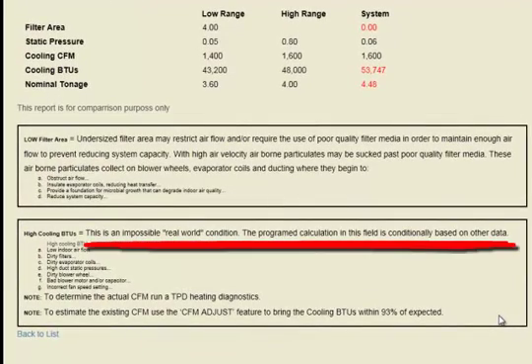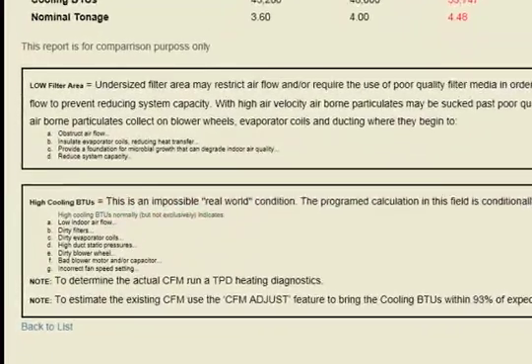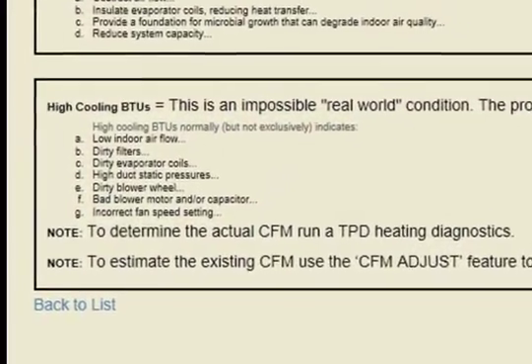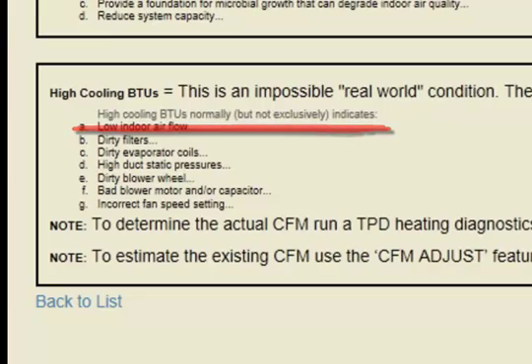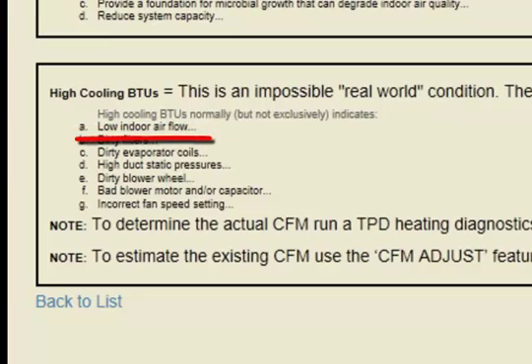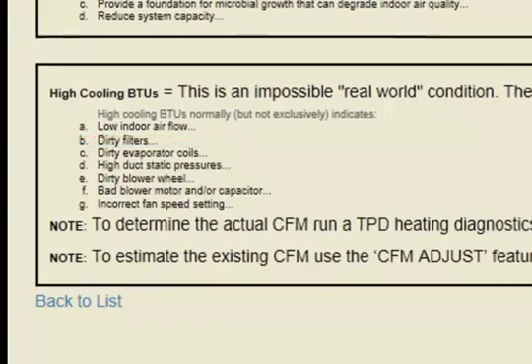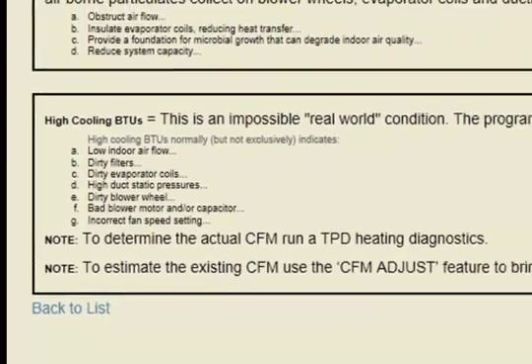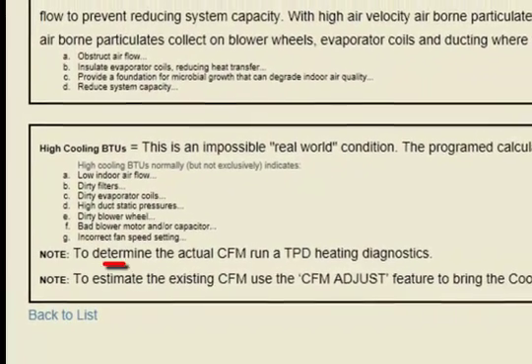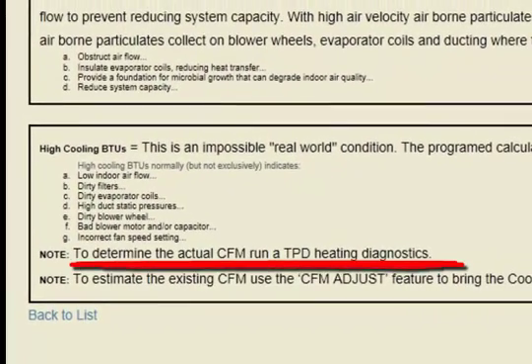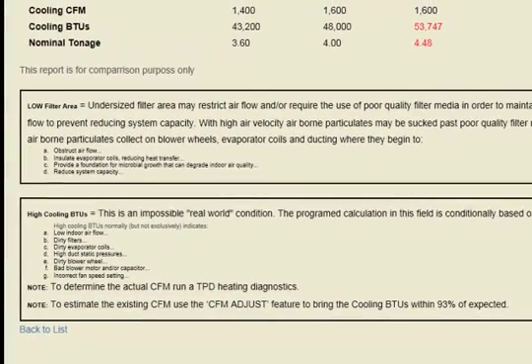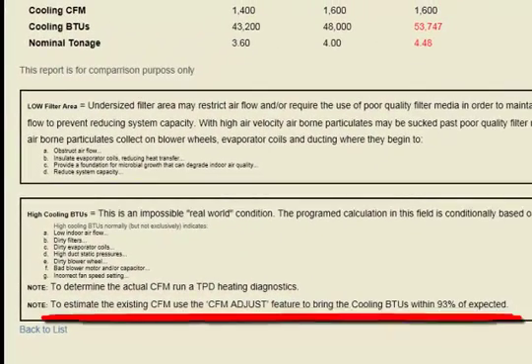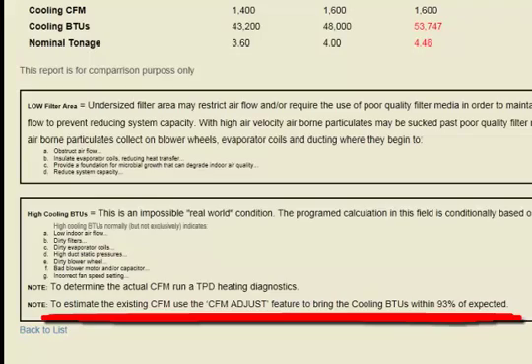The program calculation in this field is conditionally based on other data. High cooling BTUs normally, but not exclusively, indicates low indoor airflow. To determine the actual CFM, run a Total Performance Diagnostics Heating Diagnostics. To estimate the existing CFM, use the CFM Adjust feature to bring the cooling BTUs within 93% of expected.